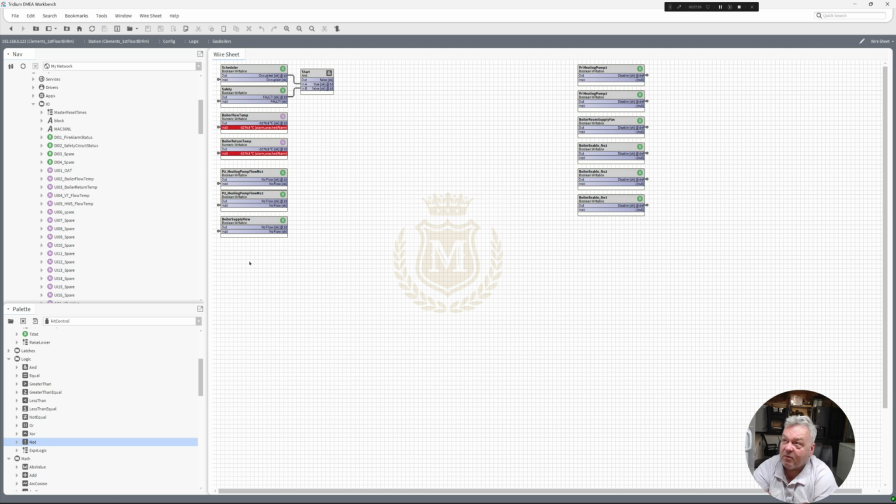So yes, we may be a case that we want to de-hum if they're going that advanced, i.e. we've got high humidity, we cool the air that's coming into the AHU with a cooling coil if it's got one, and then we reheat it back up. Yes, we're using energy, yes, we're using heat in the summertime, but I don't think they're that advanced, the air handling units. The gas boilers are never going to be off, because we've got pools, a small pool and a large pool, swimming pools. So we don't want to turn the gas boilers off if it's 28 degrees outside. So no, we're not going to put outside there. I've answered my own question there now.